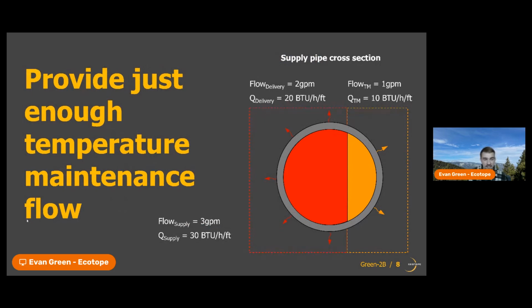And it's funny that I use this 30 BTU number after Christoph's presentation that I agree with as a standard of 30 BTUs per hour per foot of heat loss. But it does make the math really easy as we talk about this. So if we assume that we're losing 30 BTUs per hour per foot of pipe associated with this 3 GPM flow, we can then break that flow into this delivery flow, which is going to the fixtures, and then the temperature maintenance flow that's circulating through the entire loop and going back to the heating plant. And so if our fixtures are using 3 GPM, then we've satisfied our entire minimum flow rate requirement, and those fixtures are going to see 115 degrees Fahrenheit.